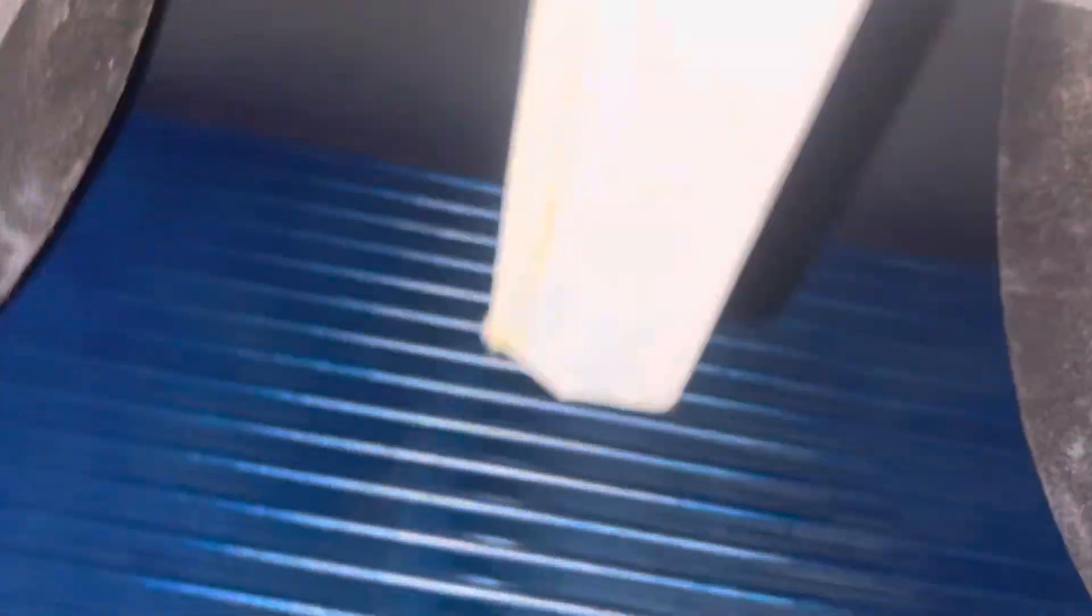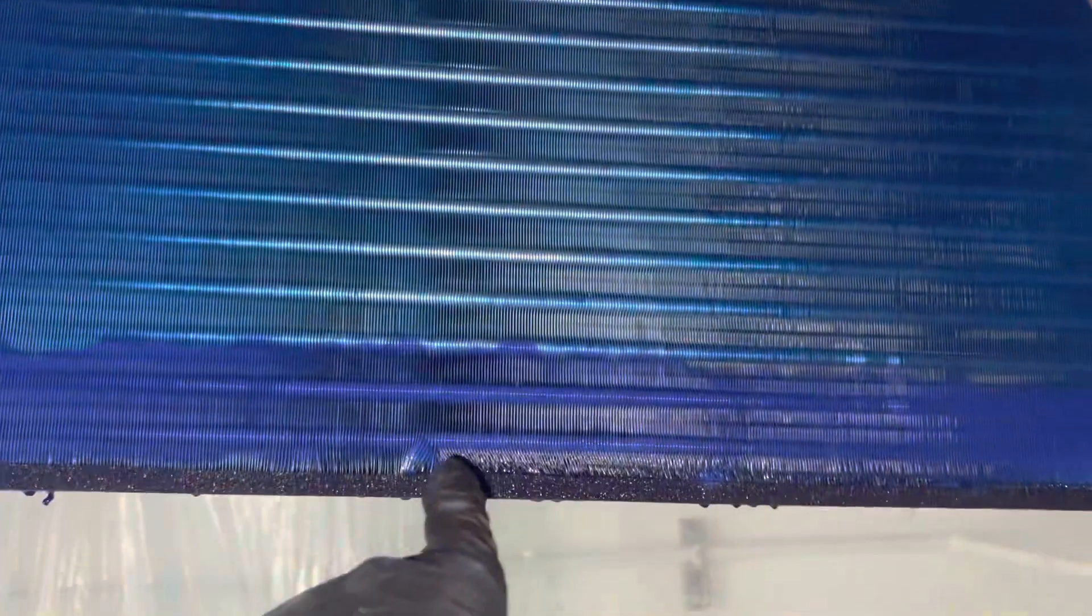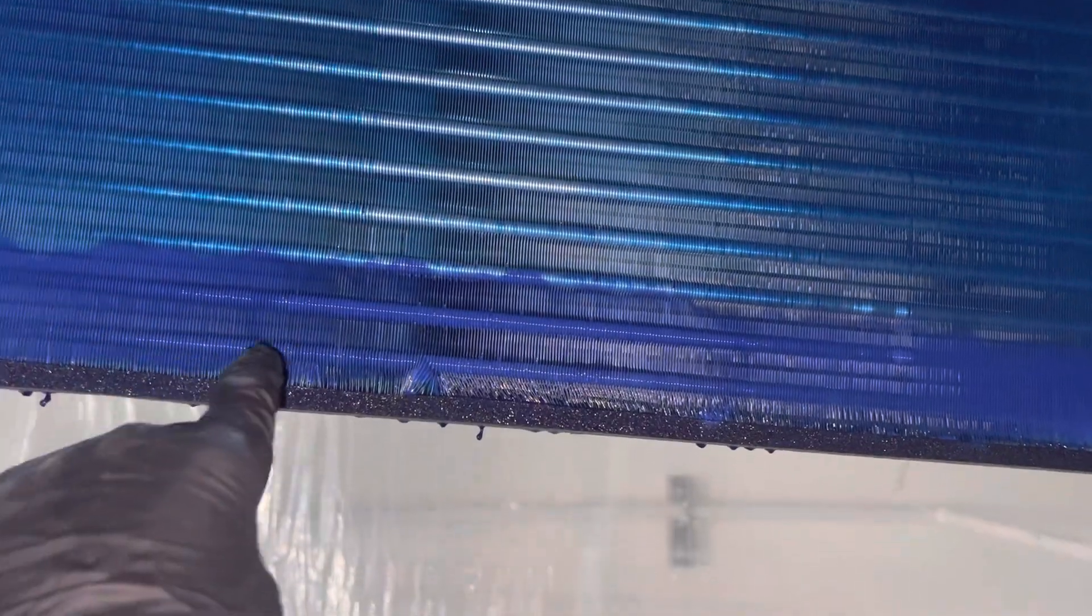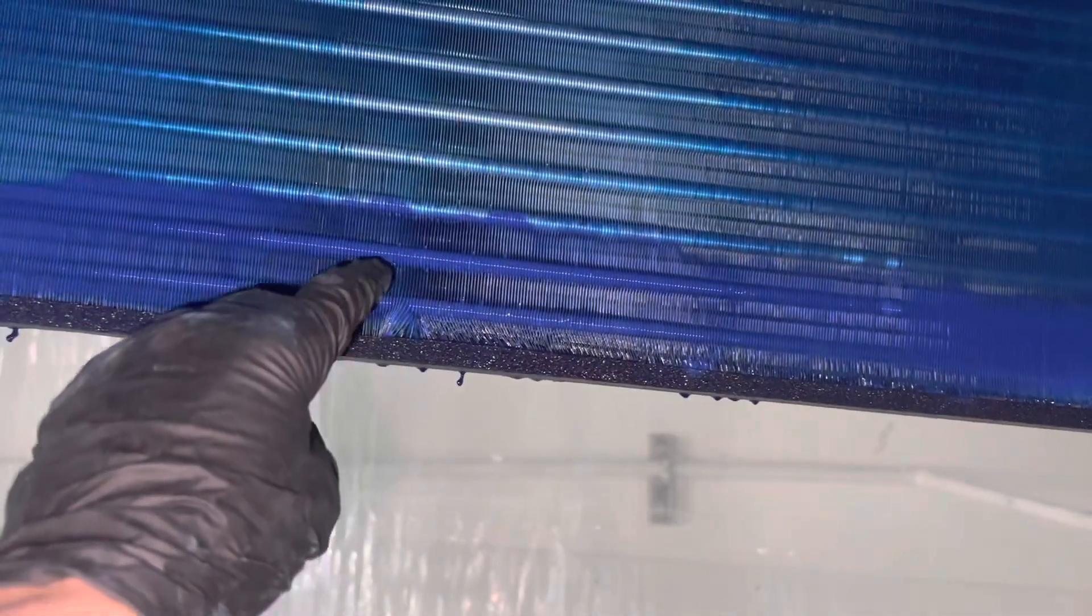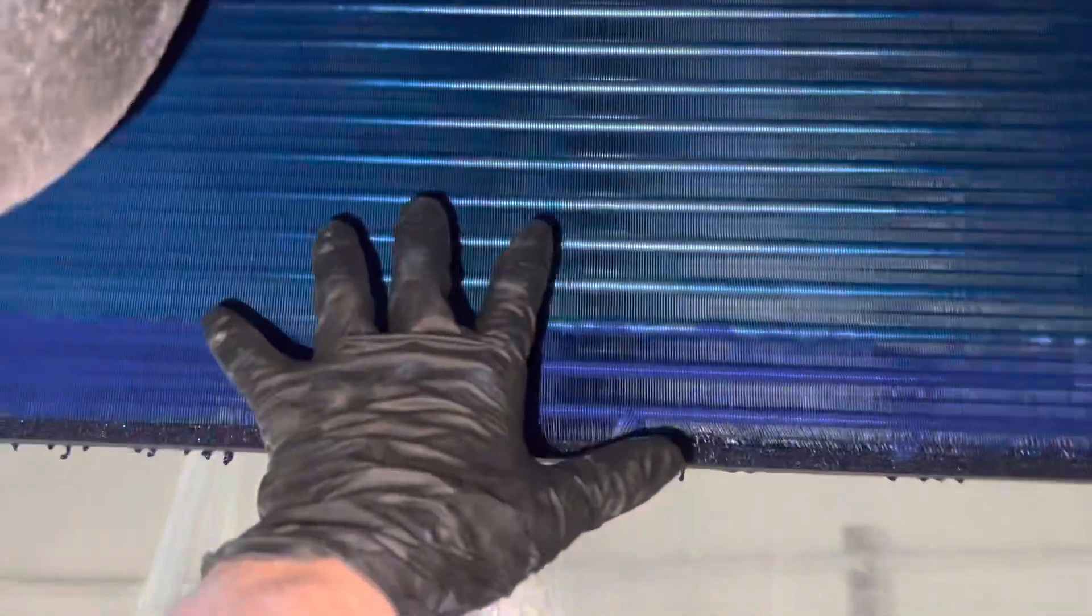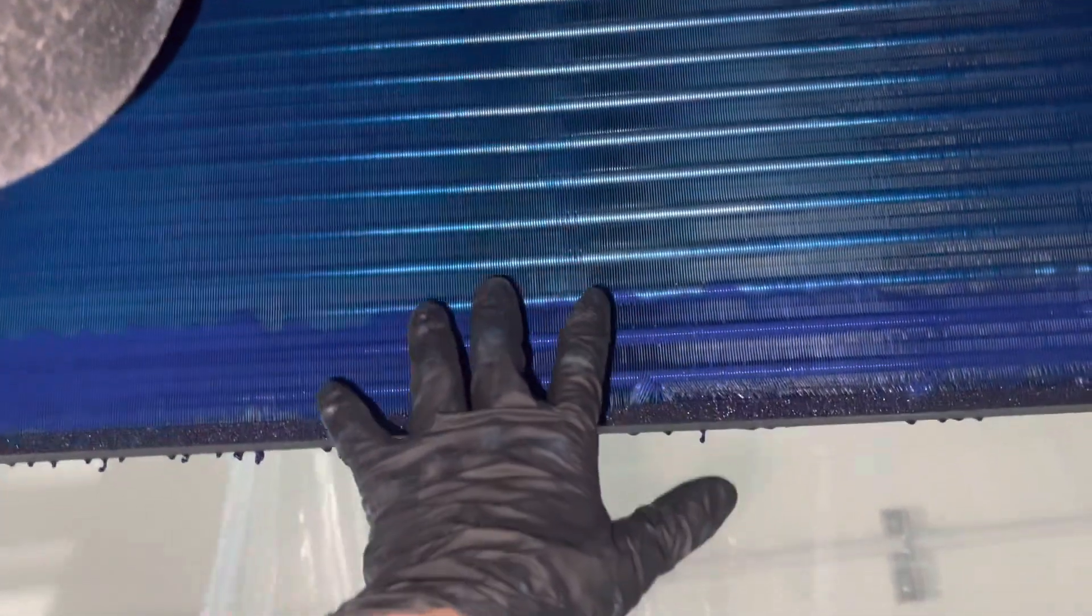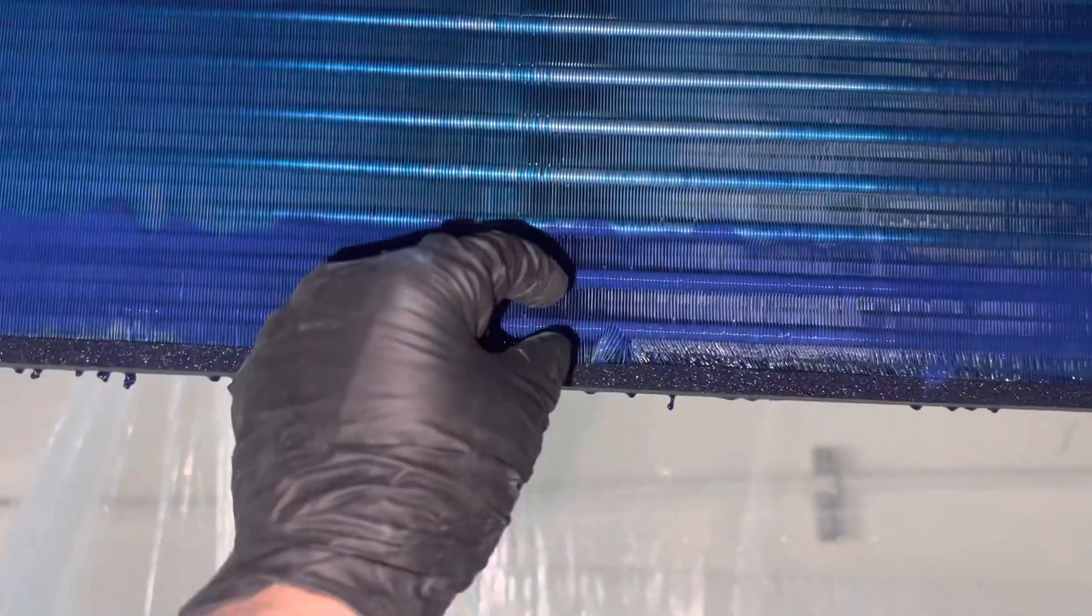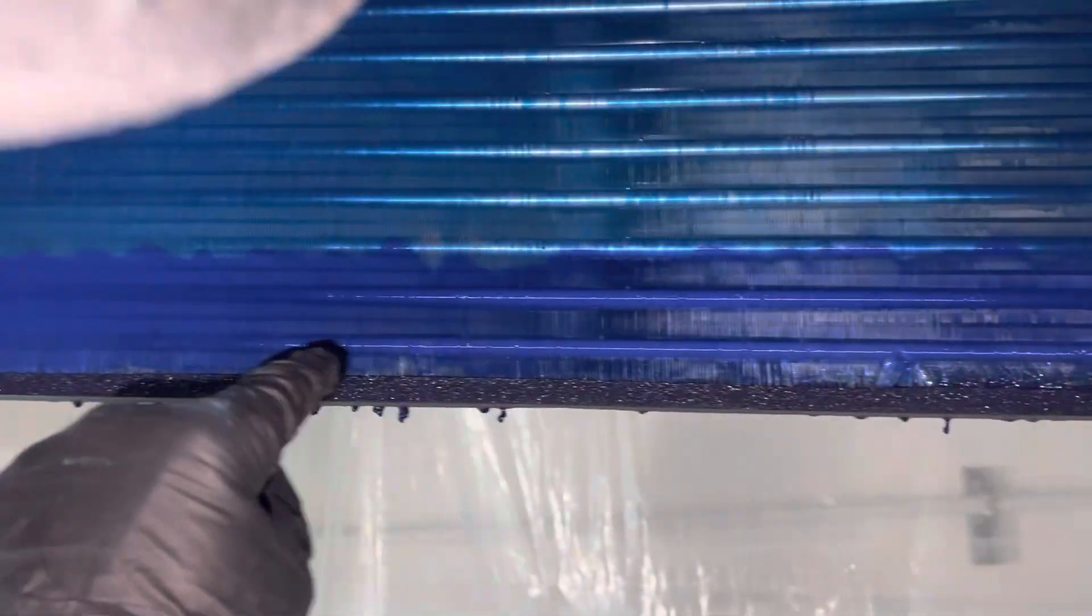I have light coats on all the upper fins, but as you can see the difference in color down here, I have three heavy coats just on the last two tubes. This is where all the filth and chemicals come dripping down in the water. This bottom section that sits down in the pan always stays wet.